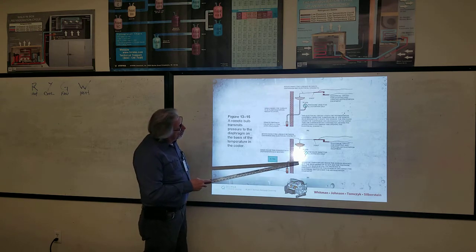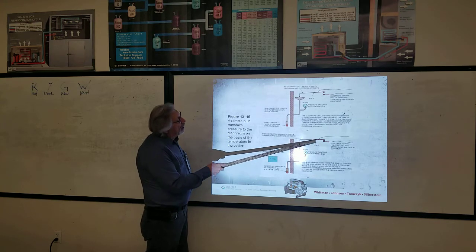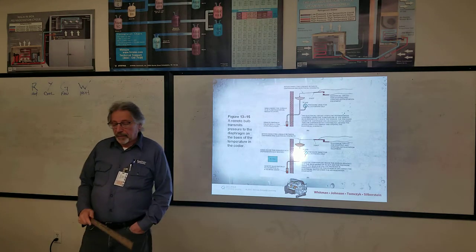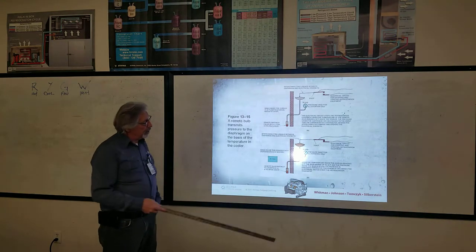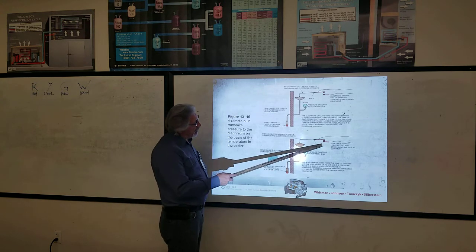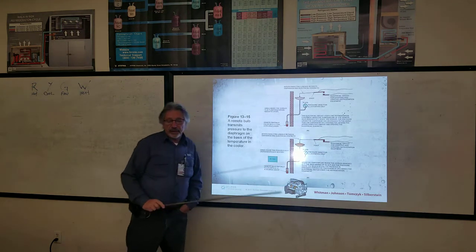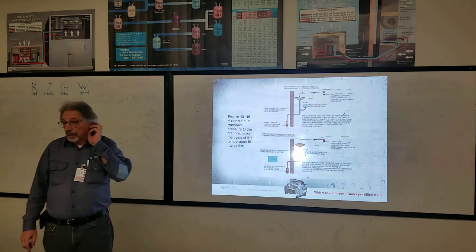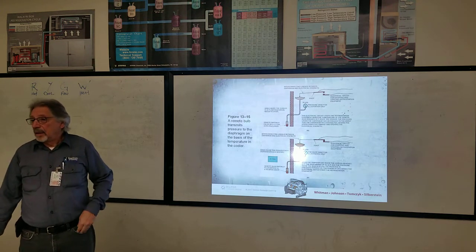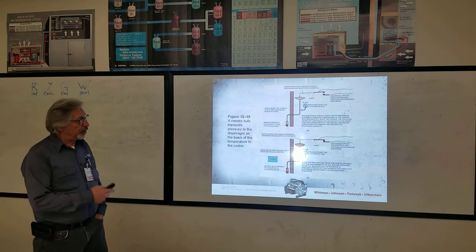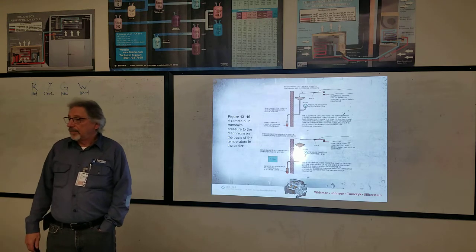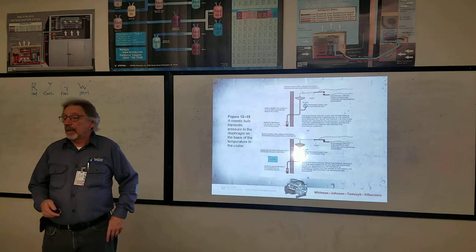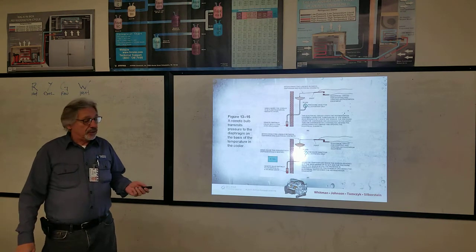It puts pressure on the tube and moves that diaphragm, and it pivots and closes a set of contacts. The contacts electrically start the condensing unit to start the refrigeration cycle to cool down the box. Isn't that exciting? Even though it's a pretty crude demonstration, that's basically how the diaphragm control is used.